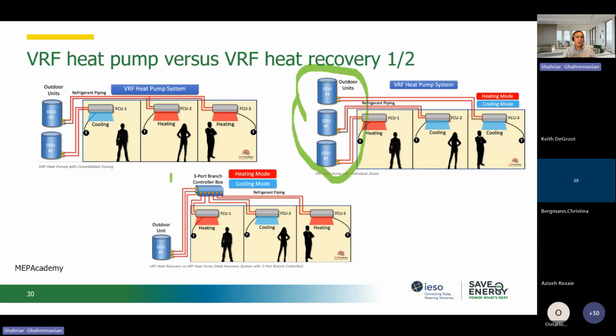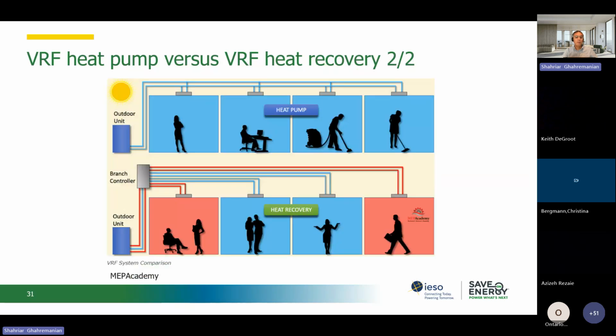We can have a branch controller. In the branch controller, we just install one unit, and based on the thermostat setting, it decides to send heating or cooling refrigerants. But maybe this area requires cooling, which means the heat needs to be taken out. So instead of taking the heat to the outdoor unit, why not take the heat to the branch controller, and then the branch controller brings it back to another environment?